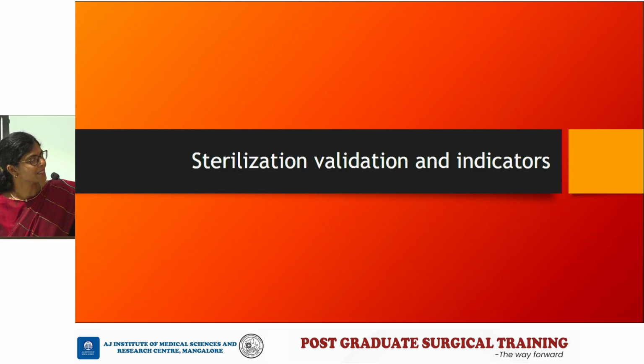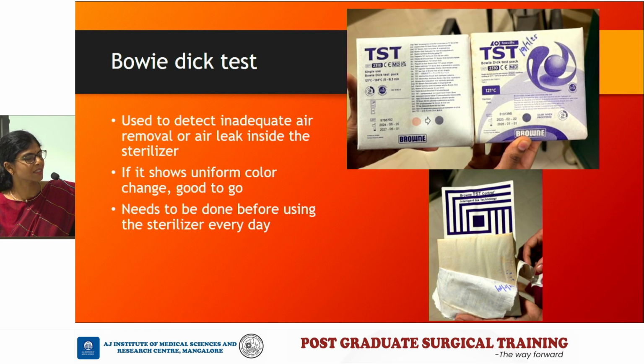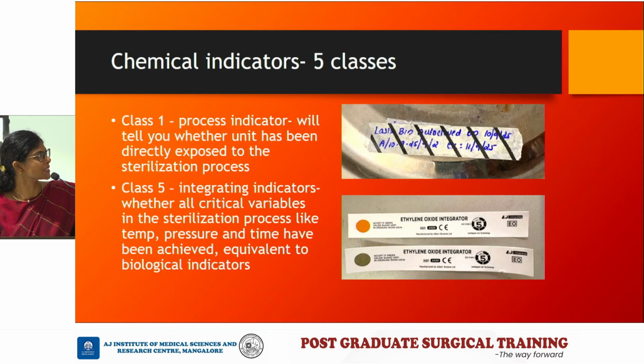So coming to sterilization validation and indicators, this is called as the Bowie-Dick test. It is used to detect inadequate air removal or air leak inside the sterilizer. So this is a set of towels which are like 100% preconditioned towels which are placed inside the sterilizer, the autoclave, and the autoclave is run for about 3 to 4 minutes, and if it shows a uniform color change, then it is good to go. This ideally needs to be done before using the sterilizer every day, but generally not done. Usually the Bowie-Dick test is done once a week.